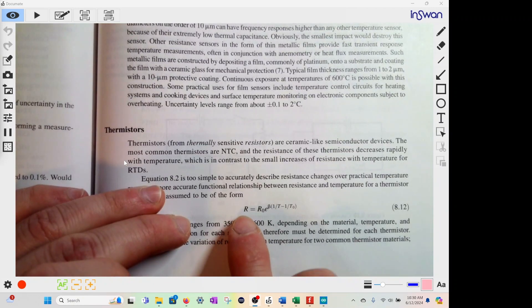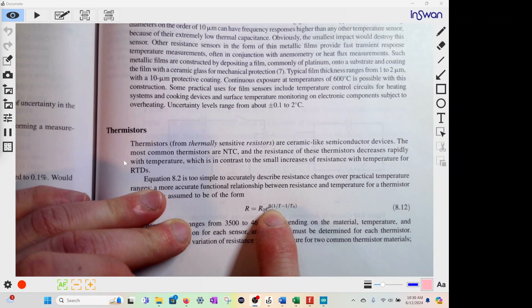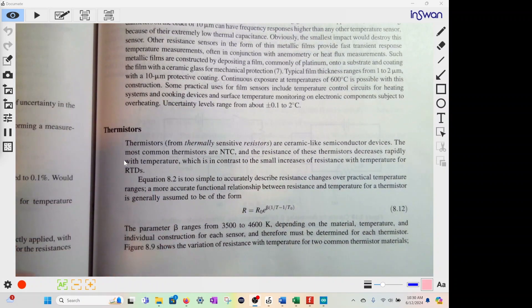The second type is a thermistor. It also changes with resistance and temperature, but in an exponential fashion. As the temperature increases, the resistance will actually decrease exponentially. The equation is R equals R-naught times e to the power of beta times (1/T minus 1/T-naught). Beta is the coefficient, and each thermistor will have a different beta coefficient.